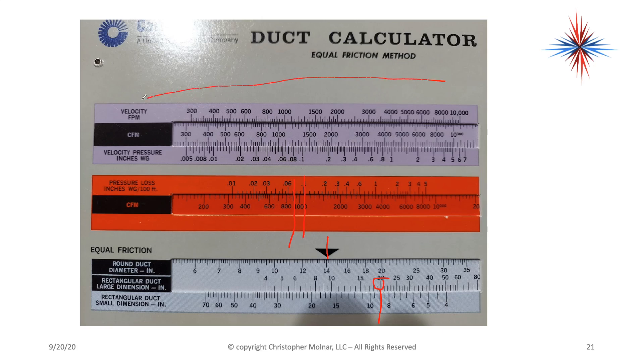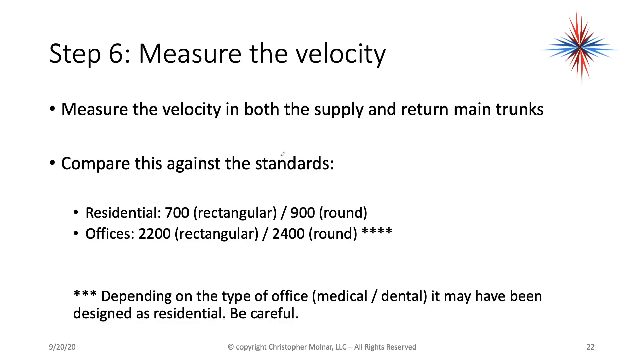Velocity is the speed of the air moving. We're also concerned about velocity. If I have a velocity pressure, it takes the actual fan into account and the movement of air — you can figure out how fast things are moving based on the CFM of the duct. We measure the velocity in both the supply and return ducts and compare against standards. For most residential environments, I want 700 feet per minute in my main duct work, or 900 for round duct work. Office areas: 2,200 in rectangular, 2,400 in round.